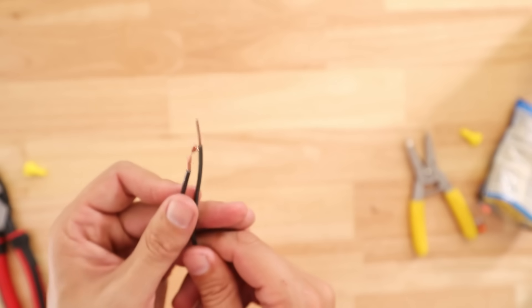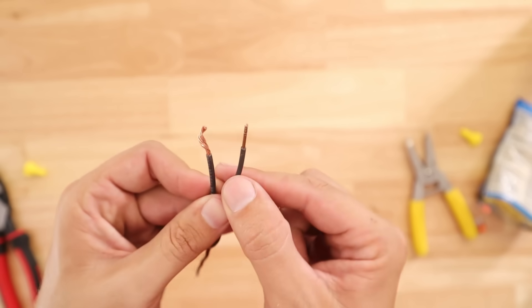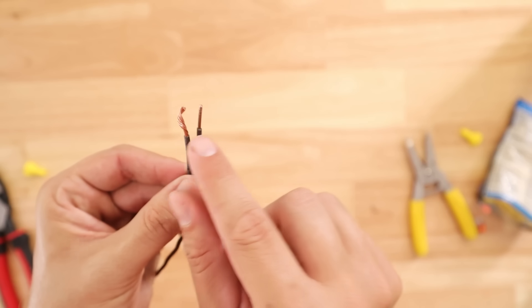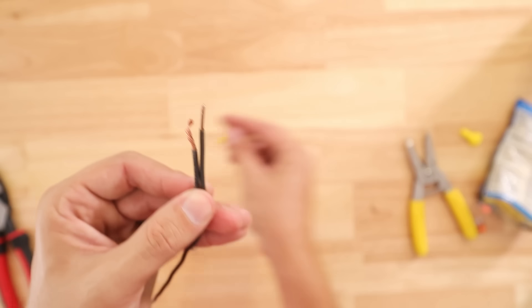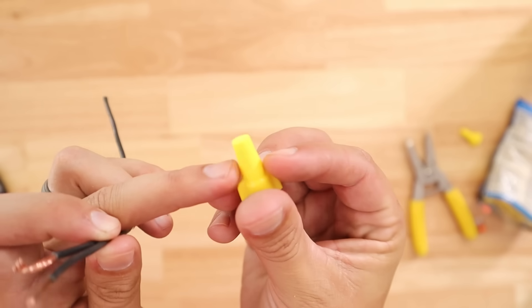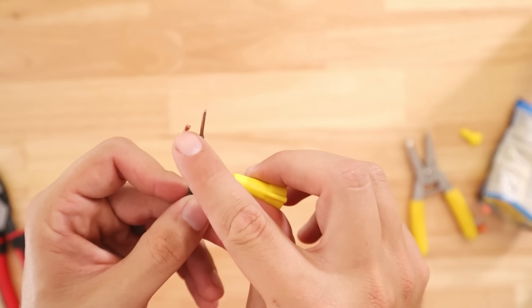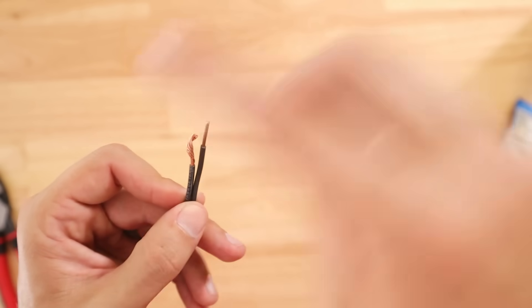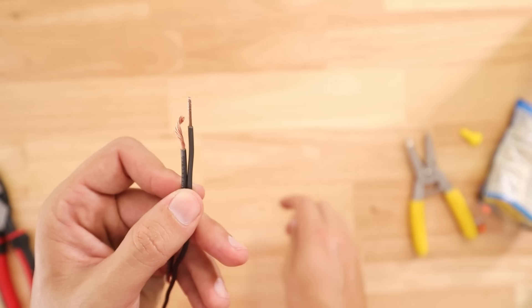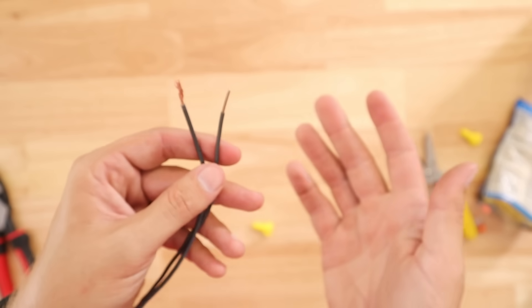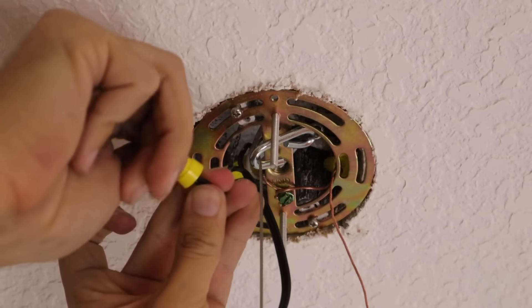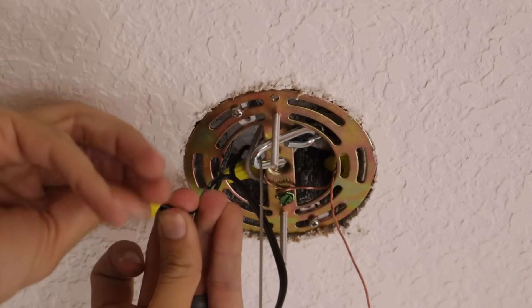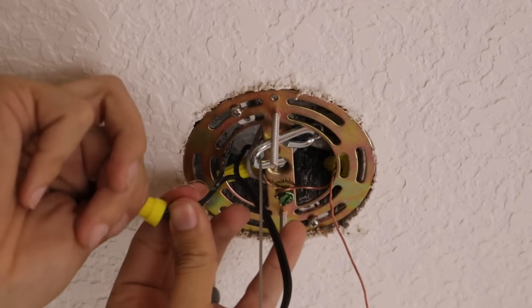And again a lot of it has to do with when they were put underneath of the wire nut you tried to put them up equally this stranded dropped down below so it did not seat up in the top of the wire nut well enough to really get a hold of it and bite into that stranded to really wrap it around the solid core wire. And I see this most often on light fixtures because a lot of times your light fixtures come with your stranded wire and of course your Romex that's running through your walls is always solid core.